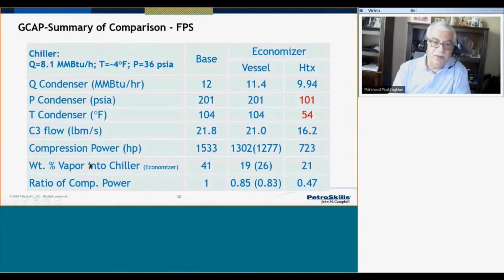Very good match. So to summarize what we obtained, the base case, which was the simple refrigeration system, for the design chiller duty of 8.1 million BTU, chiller temperature minus 4 degrees Fahrenheit, which corresponds to 36 psi chiller pressure, we get the condenser duty of 12 million for the base case. If I use an economizer, a flash tank economizer with two stages of compression, 11.4. If I use cooled process gas available as my cooling media, 9.94.